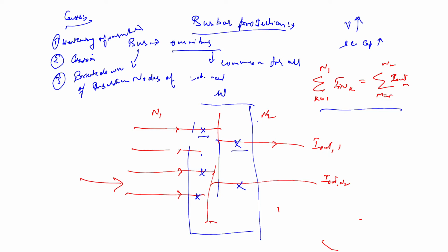If you see the system, this is the busbar and we have incoming lines and outgoing lines. In that case we are convinced that differential protection will suit this situation, because the ends are physically near each other. We can install CTs on the two sides and simply compare the currents entering and leaving the busbar, and any discrepancy between the two will immediately signal an internal fault. In the subsequent sections we will explain this differential protection of the busbar.